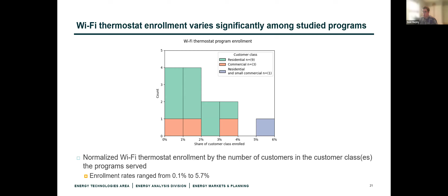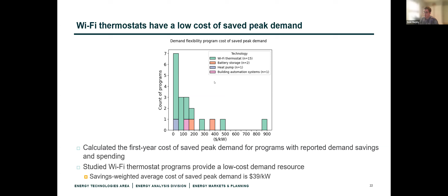We did have some data on the costs and demand reductions, and from that, we calculated a cost of saved peak demand. So that's the dollars per kW reduced on average during these events. And in particular for the Wi-Fi thermostat programs, this cost of saved peak demand was quite low. I think the savings-weighted average was $39 per kilowatt, which underscores that demand flexibility is and still can be a very low cost demand resource that's useful for grid planning purposes.